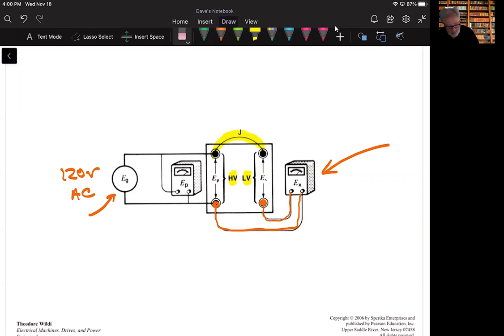We also connect another voltmeter on the other side — this is our primary voltage, E sub P — across the high voltage winding. Notice, and this is something I always point out in class, E sub X is not connected from here to here; it's connected across the two terminals that aren't being jumpered. Make sure you understand that.